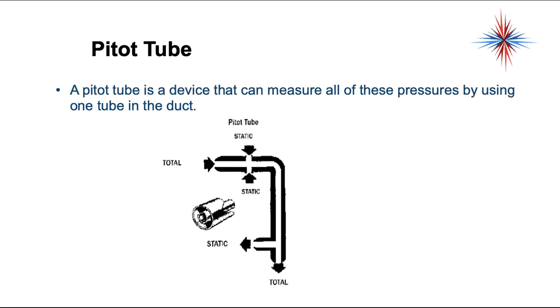The pitot tube is a device that can measure all of these pressures using one tube in the ductwork. It's basically a double-wall tool — connecting two spots on the outside gives you static pressure and total pressure. Velocity pressure is calculated by subtracting static pressure from total pressure. You take those two measurements, subtract them, and you get velocity pressure, which is the pressure of the air feed in the duct.